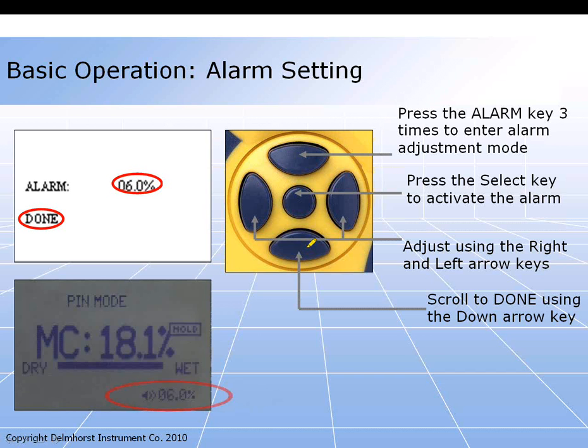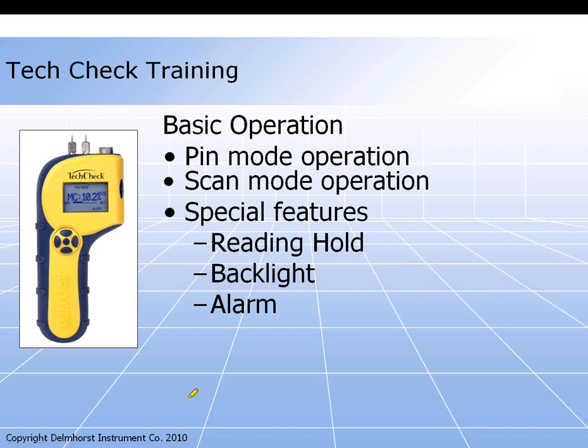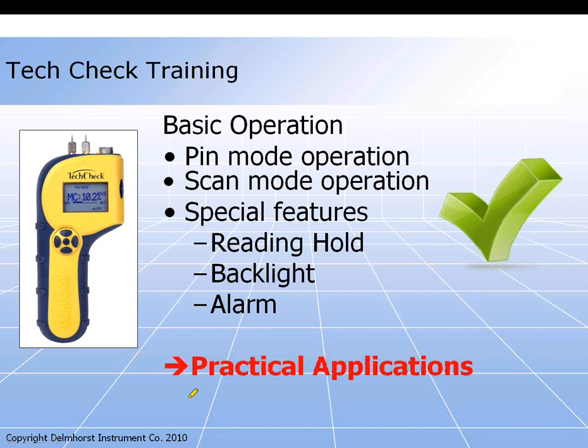I got ahead of myself here. Okay. Once you set your alarm, the value of the alarm will show up in the lower right-hand corner of the screen. So if you're in pin mode, it'll tell you it's set at 6%. If you're in scan mode, it would just have a number from 0 to 300, whatever you set your alarm to. So that's the basic operation of the meter. We covered how to use the pin mode, how to use the scan mode, the special features, which are the reading hold, the backlight, and the alarm. And now I'm just going to spend a couple of minutes on some very basic practical applications.